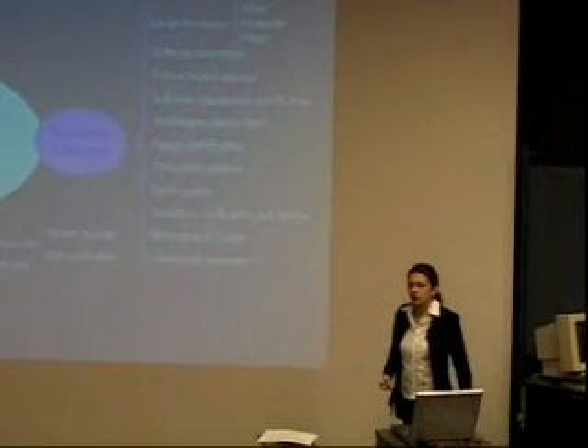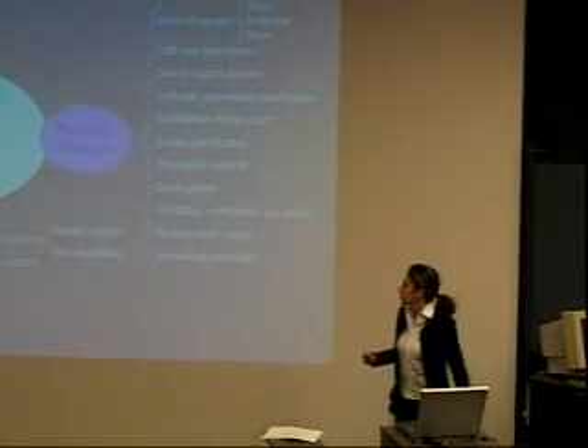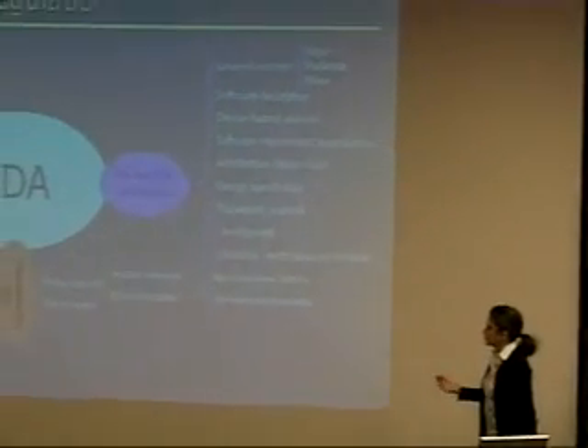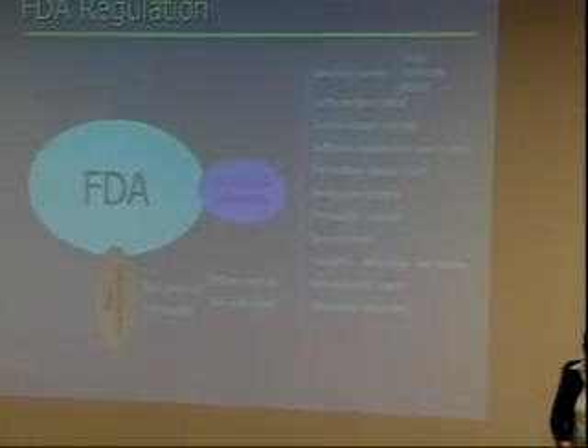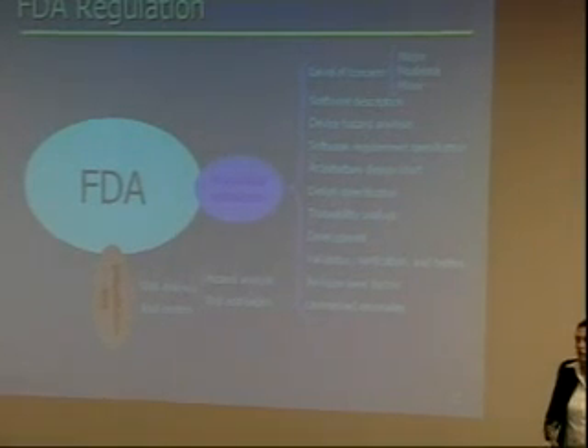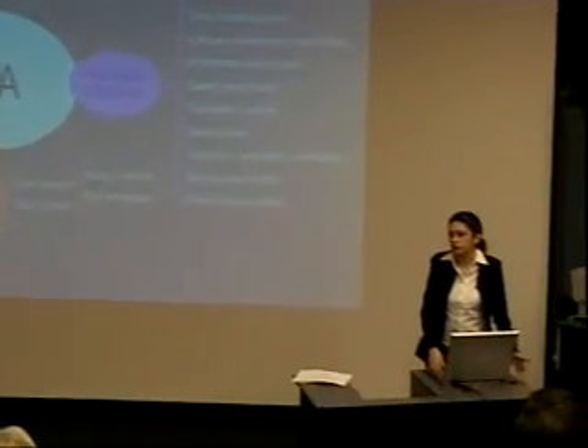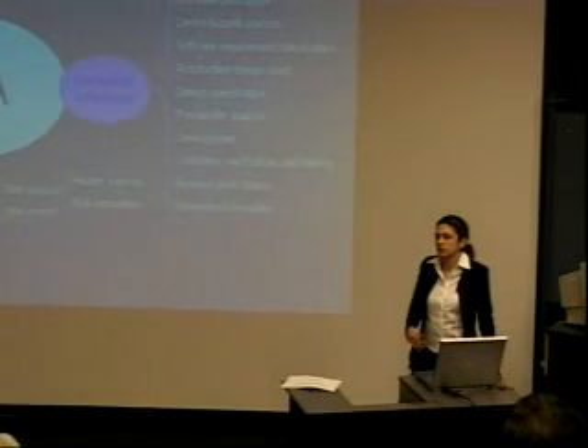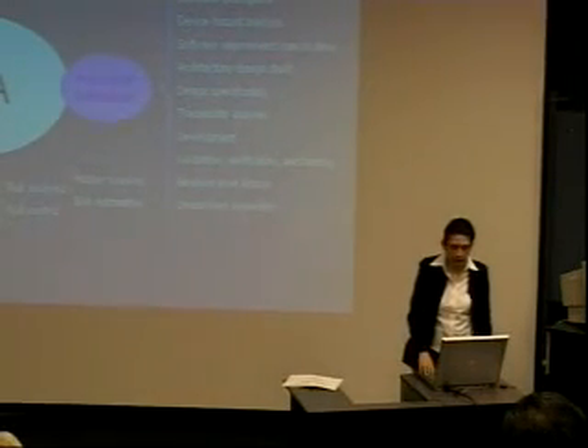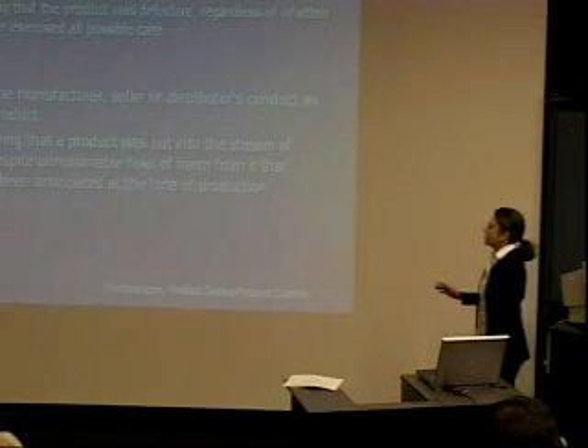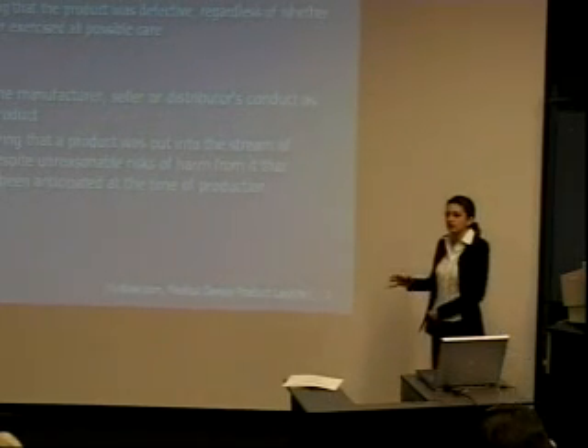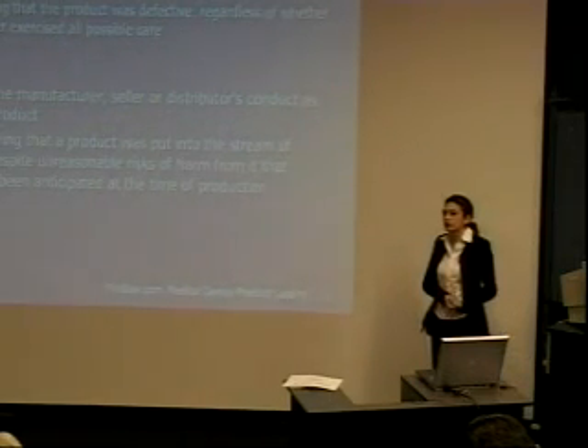The risk analysis includes the hazard analysis. That means that we have to find what the hazards of a specific medical software are, what the root causes are, and what has been done to reduce the level of the hazard. If the hazards get executed, how can we control that? And also the risk estimation: what is the risk associated with each hazard? And also the risk control: what actions are performed to mitigate the level of the risk to an acceptable level?